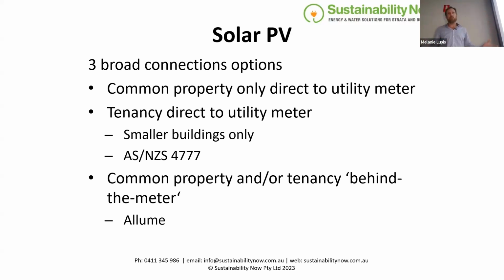It's about 15 to 20 grand for the box that can distribute solar to 15 apartments — 15 single-phase connections, or 5 three-phase connections. So ideally, if you had a building with 14 apartments and one common property meter, you'd connect all 14 tenancies to that box plus one phase to the common property meter, giving full utilization of the box. And you can stack the boxes as well.